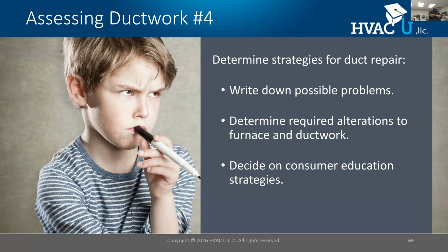The second part you hit right on the head. The purpose of the duct leakage test is to quantify duct leakage. That's the purpose of that tool. What is the leakage rate of the duct system? Just like we get a leakage rate on the blower door, same principle. So they're both evaluating duct leakage, but they have separate meanings. The pressure pan is evaluating duct leakage to the shell. The duct leakage tester is evaluating total duct leakage.